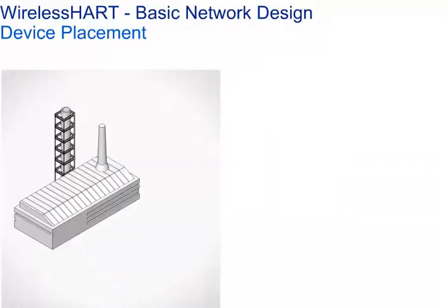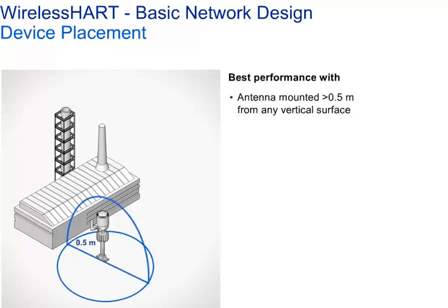Like any wired device, the WirelessHART device can be positioned in accordance with the requirements of the measurement task. Nevertheless, some aspects in the direct vicinity of each field device must be considered in order to ensure optimum wireless communication.